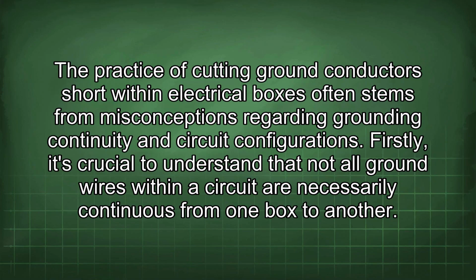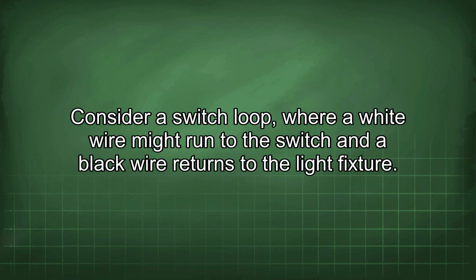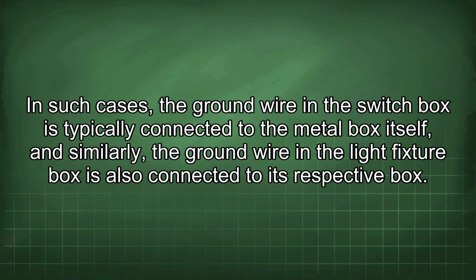The practice of cutting ground conductors short within electrical boxes often stems from misconceptions regarding grounding continuity and circuit configurations. Firstly, it's crucial to understand that not all ground wires within a circuit are necessarily continuous from one box to another. Consider a switch loop, where a white wire might run to the switch and a black wire returns to the light fixture. In such cases, the ground wire in the switch box is typically connected to the metal box itself, and similarly, the ground wire in the light fixture box is also connected to its respective box.